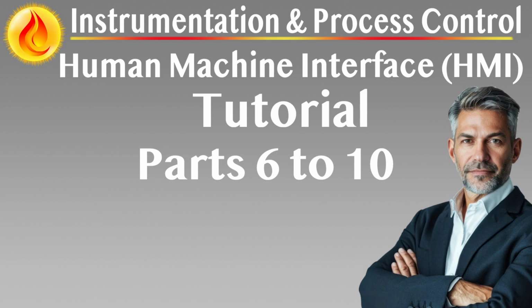Every graphic should support a clear control goal, whether it's balancing a furnace, managing a distillation tower, or isolating a pump for maintenance. Graphics should generally be oriented left to right, with process streams and control signals entering from the left and exiting to the right. This directional logic mirrors the reading flow and simplifies process comprehension. Vertical scrolling should be avoided wherever possible. Horizontal flow is easier for operators to interpret quickly.